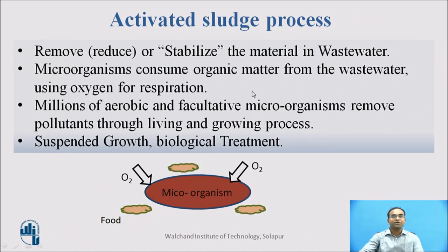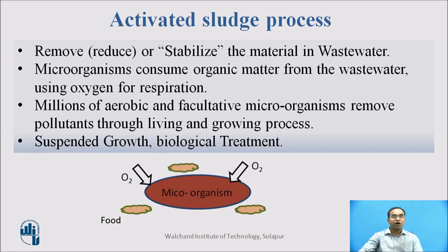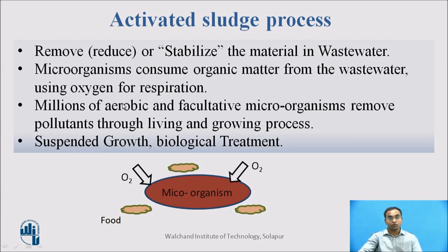What is activated sludge process? Basically, activated sludge process is a suspended growth biological treatment. Whatever biological matter is present in the wastewater will be in suspension form in the secondary plant. How can we treat that carbonaceous matter? We add some microorganisms which are aerobic or facultative in nature. Aerobic means the microorganisms require oxygen for their own growth. Facultative means those microorganisms which can sustain themselves with or without oxygen. These microorganisms will stabilize the material in the wastewater.